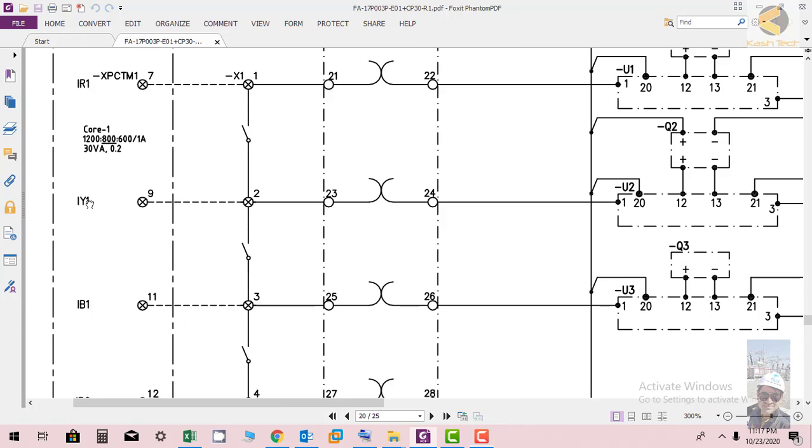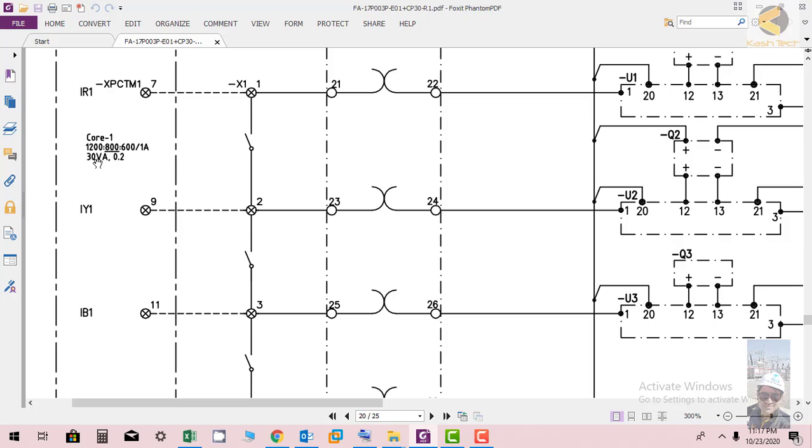The CT has three ratios and the secondary is of 1 ampere. The VA rating of the CT is 30 VA and the class for the CT is 0.2, so it's having a 0.2% error.